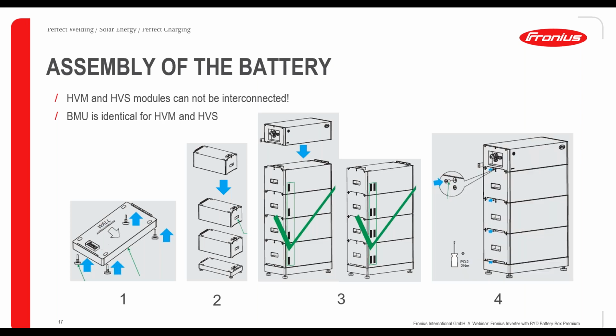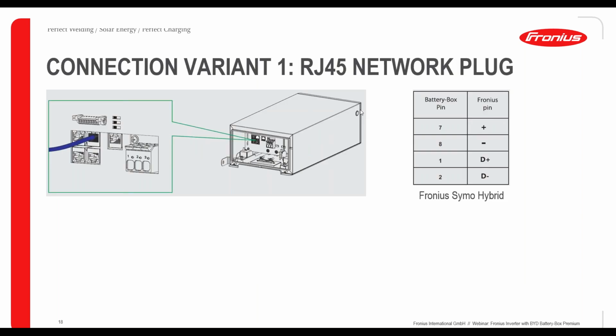This is the last module that comes on top, and the BMU module implements the connection area of the battery system as well as the data communication area. Within this BMU module, it is now possible to do the data communication to the Fronius hybrid inverter. In this case, the first connection variant is the network plug, and we recommend using such a network plug because it's the easiest, most comfortable way of connecting the battery to the inverter. As you see in the picture, you have the possibility to use the network plug and just plug it into the right upper corner of the BYD connection area. Just plug it in, and then you have 4 pin connections to the Fronius inverter.